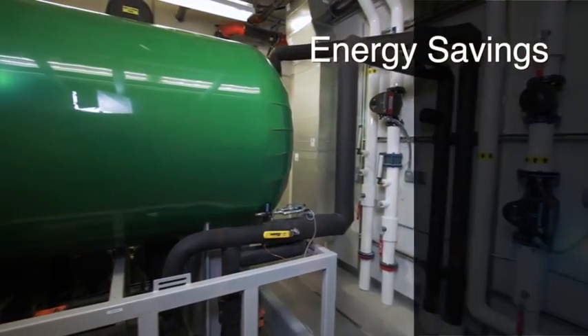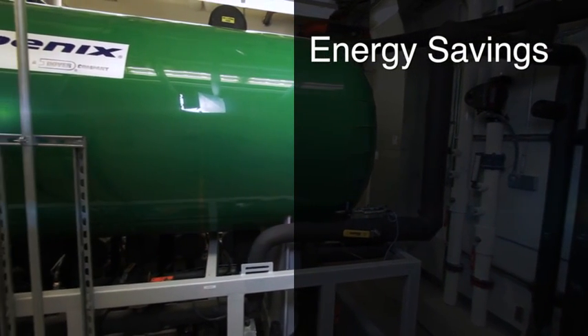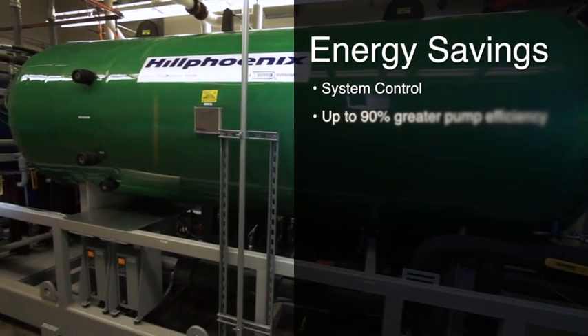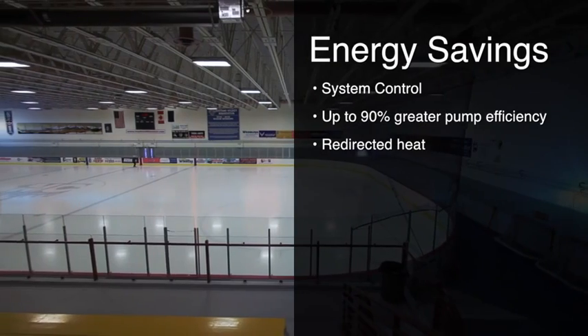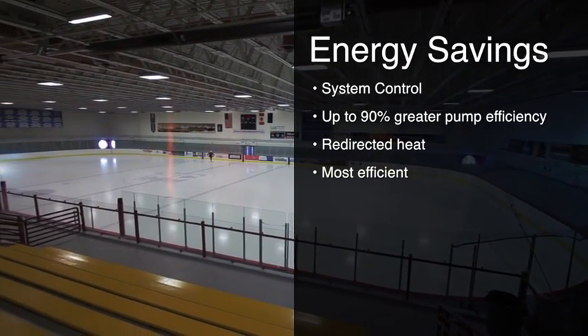The Hill Phoenix CO2 refrigeration process uses CO2 as both the natural refrigerant and the fluid circulated under the ice surface from a common liquid receiver. Due to the low viscosity and low pump energy requirements, it's the perfect fluid for an ice surface. An additional benefit to the CO2 direct system is the generous amounts of high-grade heat available for many uses in the facility. CO2 is the most efficient heat transfer fluid to apply to a direct ice system.